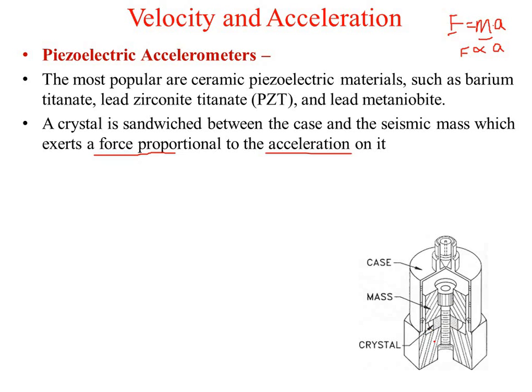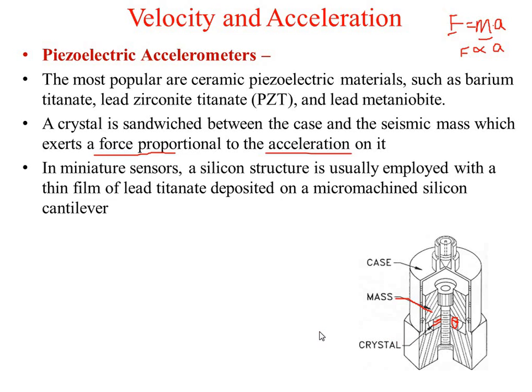Okay, so this is exactly where your crystal is. You can see that this portion is the crystal. This is the mass, and this mass is fixed. This is the case, and the crystal is here. Whenever the mass puts a pressure on the crystal, whatever the pressure that comes will create a voltage. That voltage will be proportional to the force applied, and that is proportional to the acceleration.